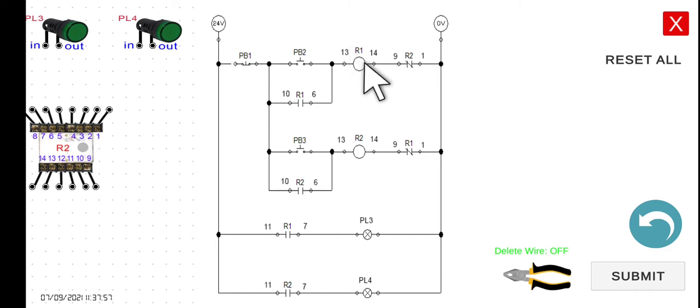Take note: when R1 is energized, the normally closed R1 interlocking contact in the R2 line opens. So no matter how we press PB3, current cannot flow — there is an open circuit, and R2 remains de-energized.